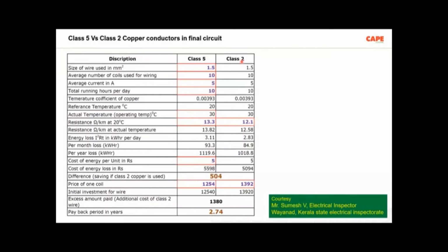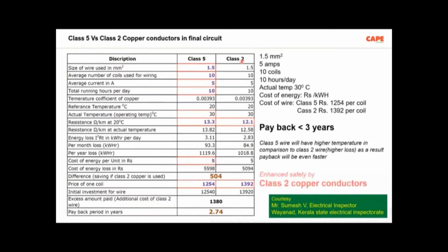Somebody asked me what is the energy loss and what is the payback period if we change from class 5 to class 2 conductor. So I just calculated, not me, it is done by Mr. Sumesh V, electrical inspector of Wayanad, Kerala state. He helped me, or he made this particular table, and finally our calculation, for example, 1.5 square millimeters of wire, imagine 5 ampere current flows through this particular wire. We took a case of 10 coils, approximately, maybe typically for a small scale industry or a small house, working 10 hours per day with an actual temperature of 30 degrees centigrade. We actually took these values in a very, very moderate way. The actual temperature is probably sometimes much higher than 30 degrees. Once the temperature is higher, resistances are also higher, then we actually end up in trouble.